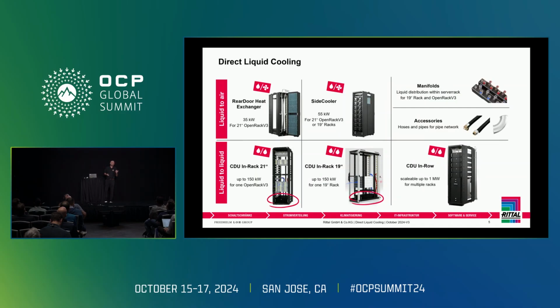The main portfolio we've developed to support this is based around liquid-to-air and liquid-to-liquid, to allow that step change from air into liquid into the future. Rear door heat exchangers, liquid-to-air, around 35 kilowatts for the OCP 21-inch product. Side cooling, 55 kilowatts for both 21 and 19-inch type products.